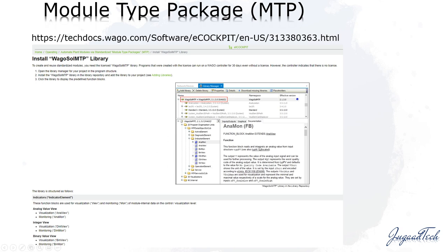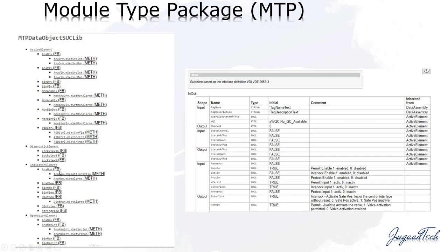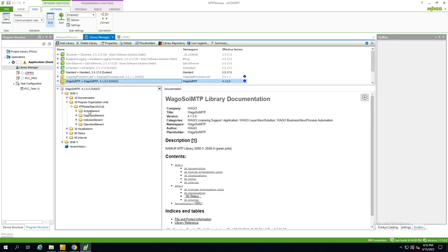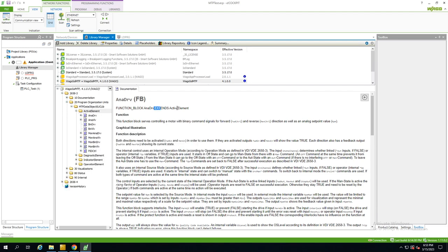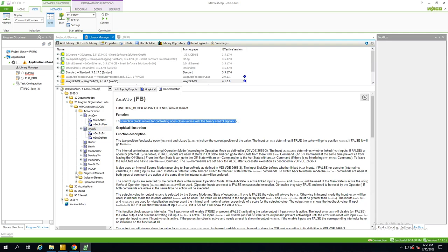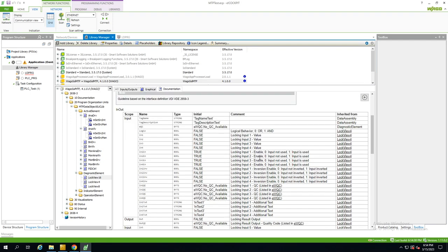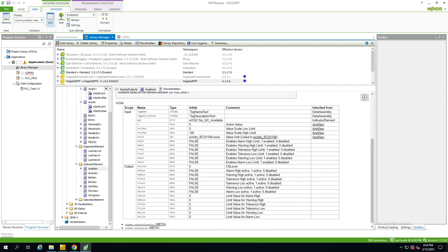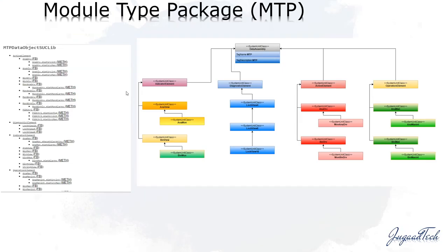The MTP structure is divided into four categories. AnaMon is inherited from AnaView — so inheritance and abstract classes are present. This is why OOP concepts come into picture, because that is the whole structure it follows. The four categories are: Active Element — for all drive modules like motors, valves, and actuators; Diagnostic Element; Indicator Element; and Operator Element — for operations. That is how the whole structure is defined.